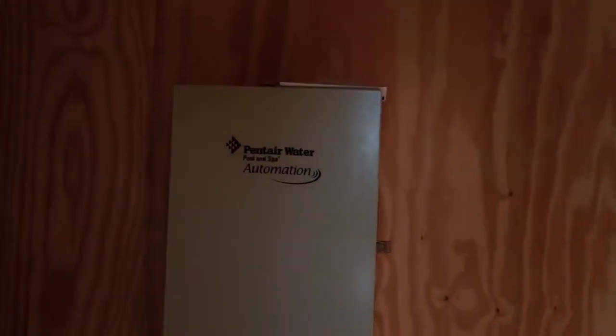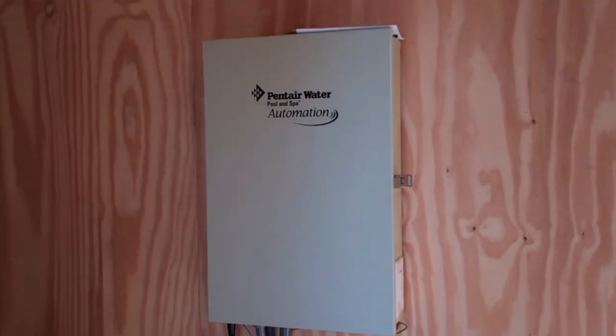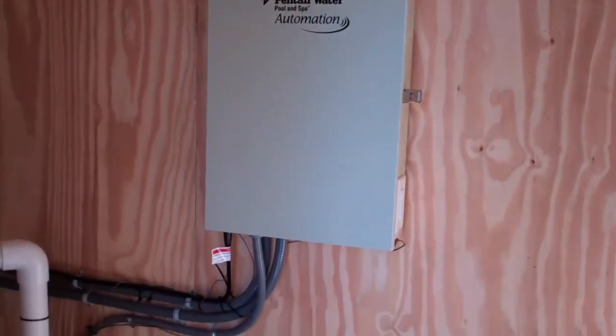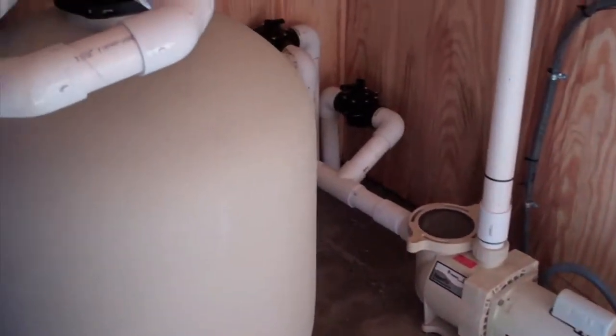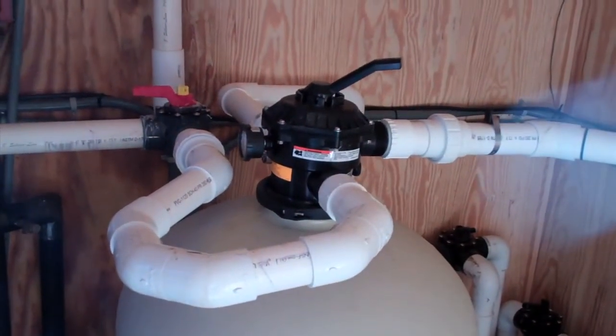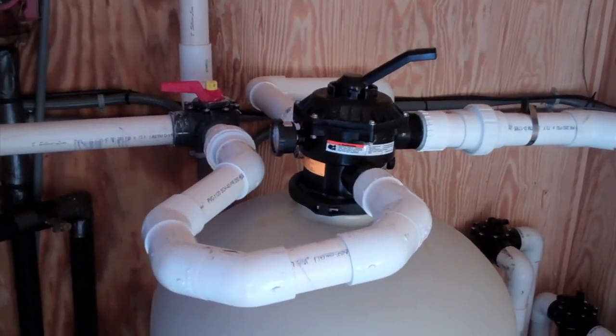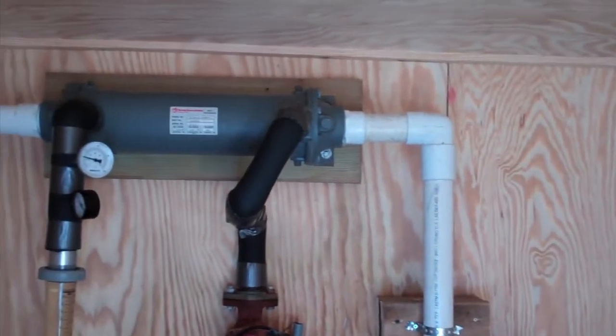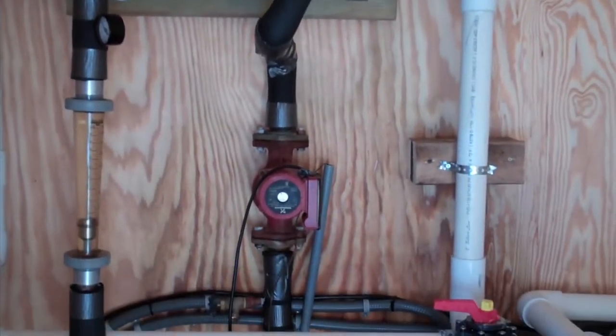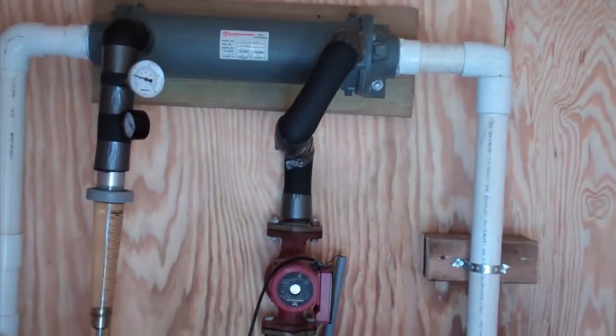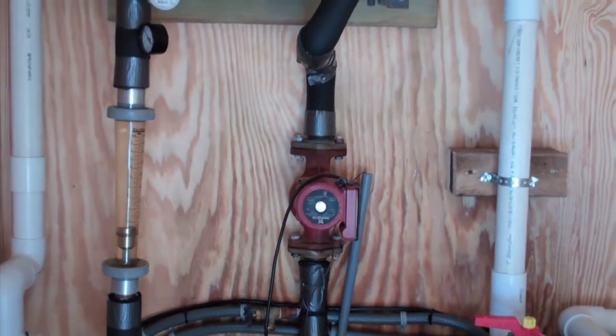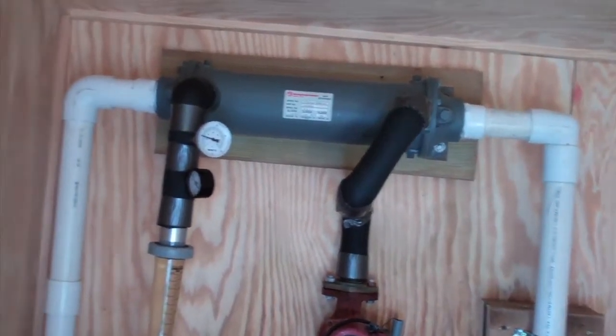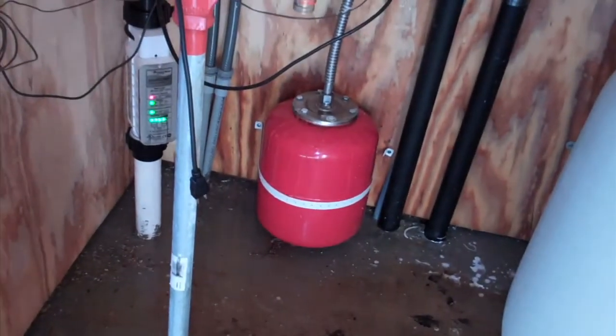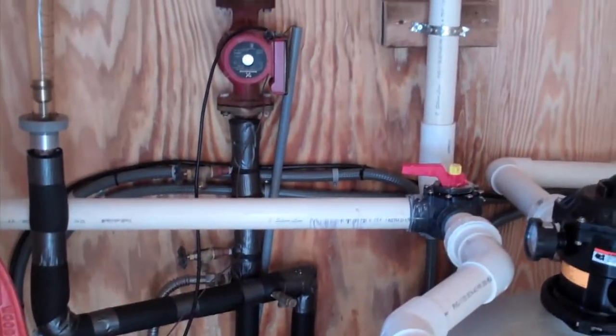Go into the pool house for a minute, and we'll see there's the controller that controls both all the pool equipment as well as the solar panels. There's a pool pump down here in the corner, the pool filter system, diverter valve which routes the water through one of various channels, one of which is up to the heat exchanger, which is connected to the solar panels. There's a solar pump that runs a closed loop circuit, and a flow gauge tells us how much water is flowing through the system. And that transfers the heat into the pool loop, which goes down into the pool. And there's an expansion tank, which is standard. And that's a pretty good sized pool system.